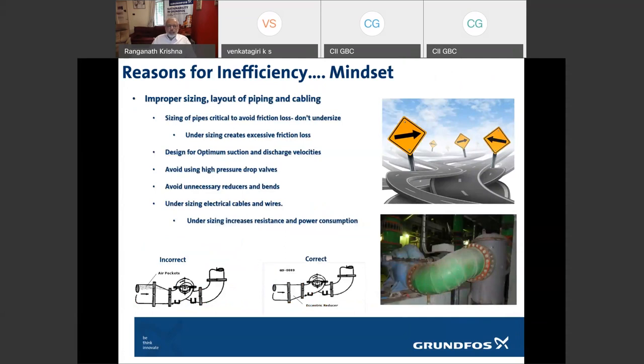The other reason for inefficiency is the sizing of pipes. Very often when you look at design, the piping design is done by somebody, the pumps are chosen by somebody else, someone gives you other data, and generally bigger pipes are more expensive, so you start cutting down the size of pipes. But the moment you undersize pipes, you create excessive friction loss. For the rest of the life of that building or that factory or that process, you'll be consuming more electricity. And normally through the life cycle, you see that you pay 4 or 5 times more in energy than for the pump or the size of the pipe. Design for optimum suction and discharge velocities. Higher velocities mean higher losses. Make sure that you have the right velocities.